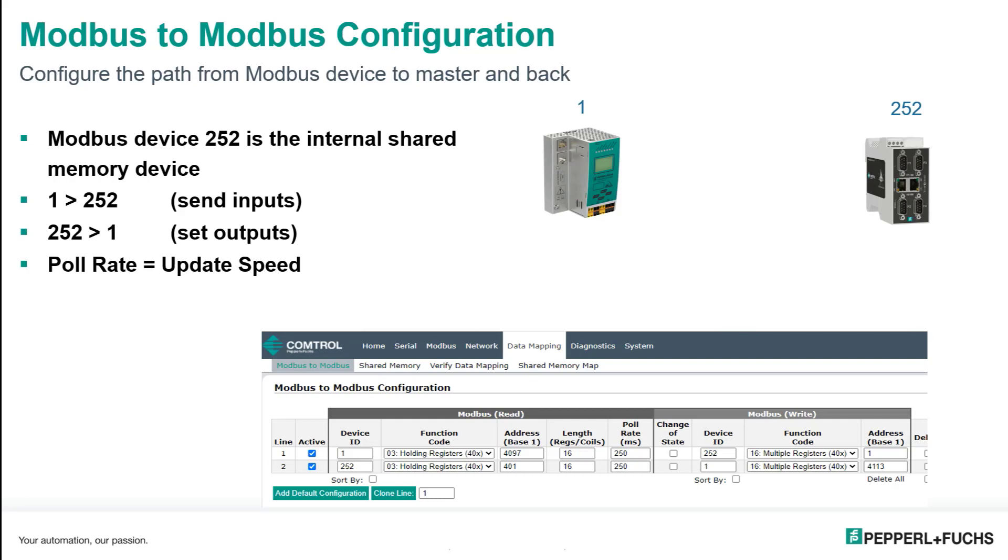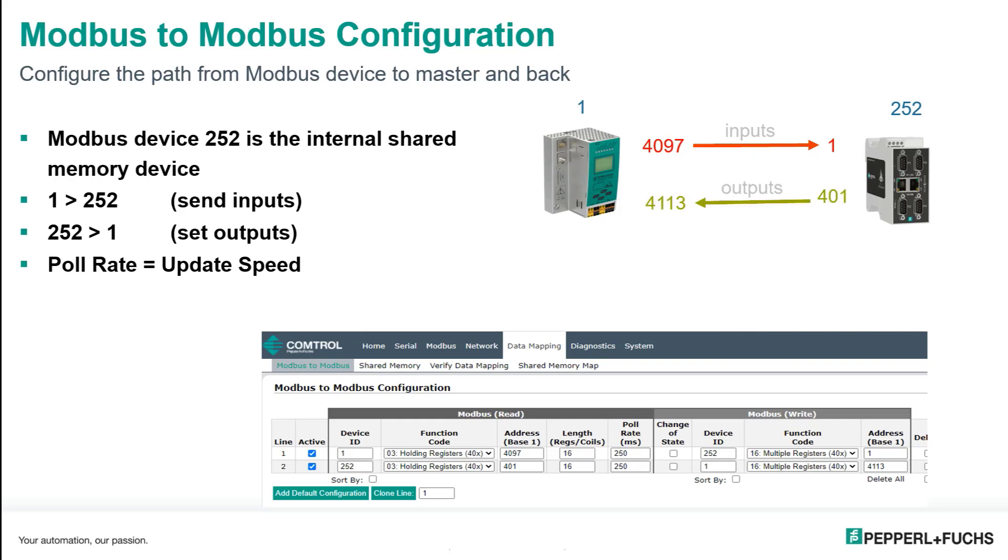The DeviceID for the device master's shared memory is defaulted to 252, so that's what I'm going to use here. So inputs at address 4097, that's where I define my device inputs, will be sent to DeviceID252 at address 1.